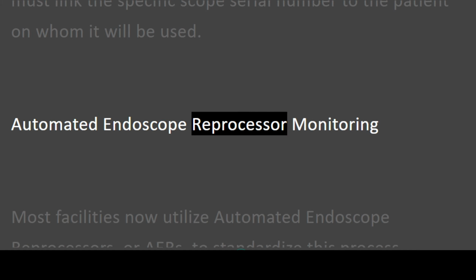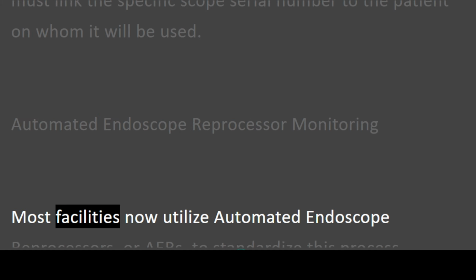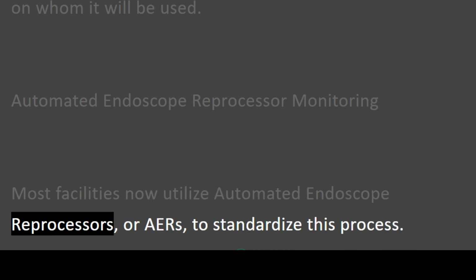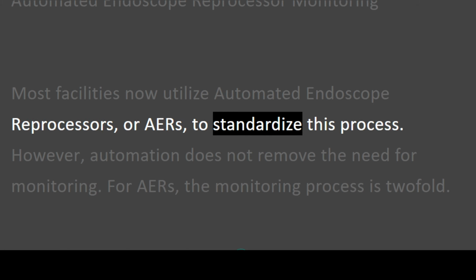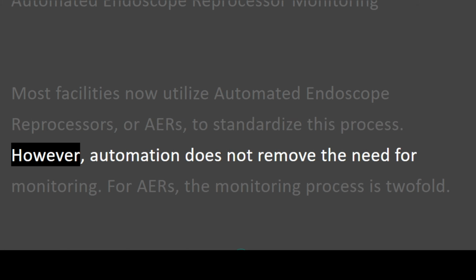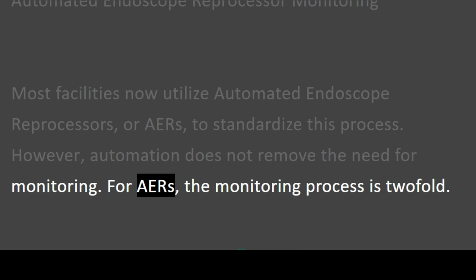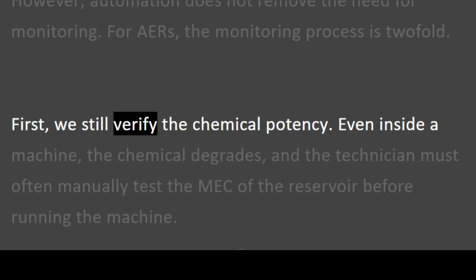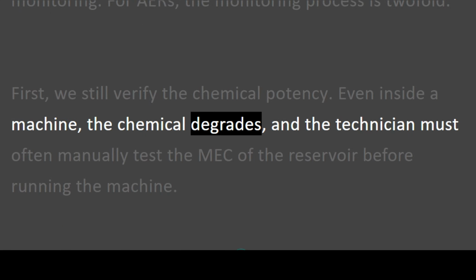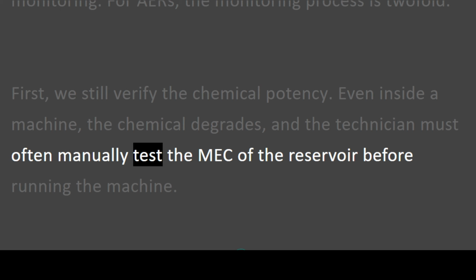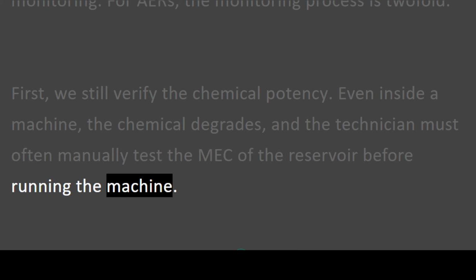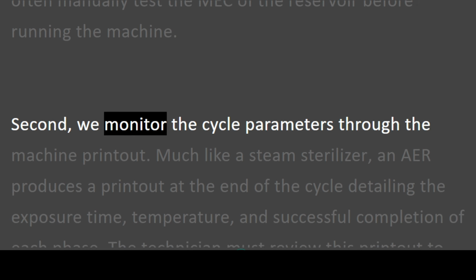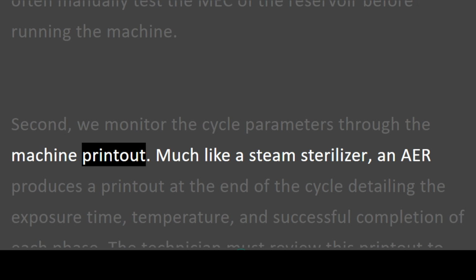Automated endoscope reprocessor monitoring. Most facilities now utilize automated endoscope reprocessors, or AERs, to standardize this process. However, automation does not remove the need for monitoring. For AERs, the monitoring process is twofold. First, we still verify the chemical potency. Even inside a machine, the chemical degrades, and the technician must often manually test the MEC of the reservoir before running the machine. Second, we monitor the cycle parameters through the machine printout.